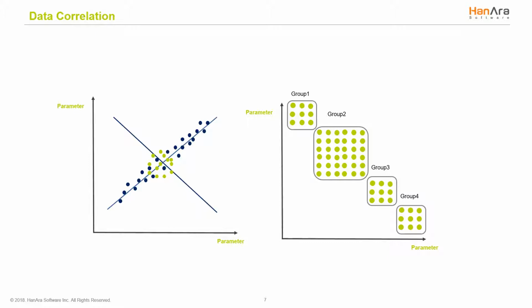Since patterns are based on normal operating data of the plant, the model also reflects the operating environment of the plant and equipment. For example, the model considers the seasons. The pattern for the summer season looks different than the pattern for the winter season. Finally, the predictive model must be optimized. Even if there's a subtle change in signal value, it can be a very important change. And even if there's a sudden change, it may be a natural change in the characteristics of the signal.